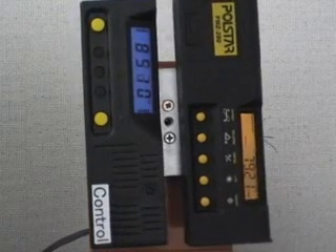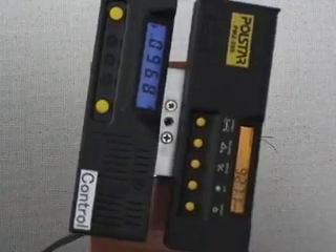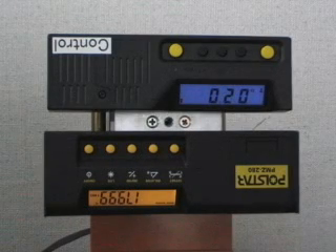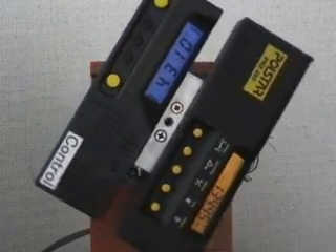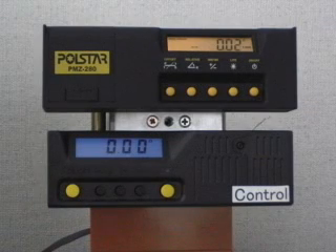At a 90 degree position, however, the control inclinometer displays minus 89.6 degrees — that is a 0.4 degree variance. At a 180 degree position, the control inclinometer displays 0.2 degrees, a 0.2 degree inaccurate variance. When the stepper is turned back to the original position, the relative accuracy of the control inclinometer is around plus or minus 0.4 degrees. However, the Polstar inclinometer is always accurate up to 1 hundredth of a degree.